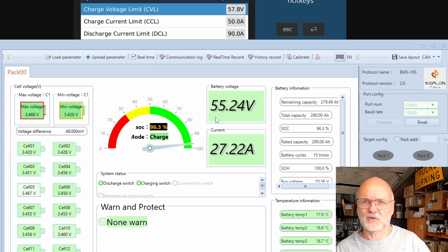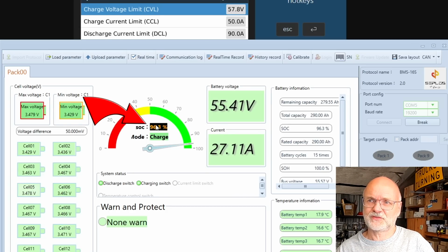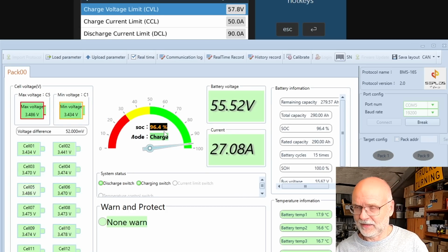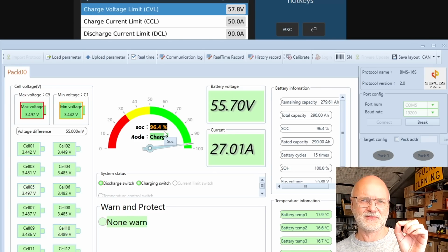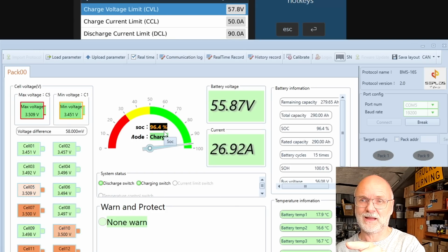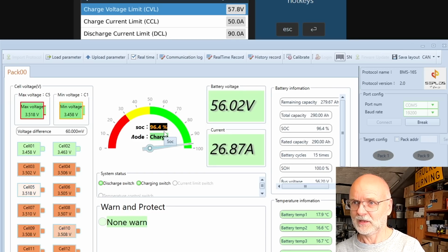55.2, this is our old absorption voltage, but now we are charging further to 57 volts. So also watch the state of charge situation here. I will note the time when we actually hit 56 volts, because this is then the trigger for this half-hour threshold, if there is one. We can see the first cells popping up now as an alarm over 3.5 volts. 56 volts, there it is, 149.